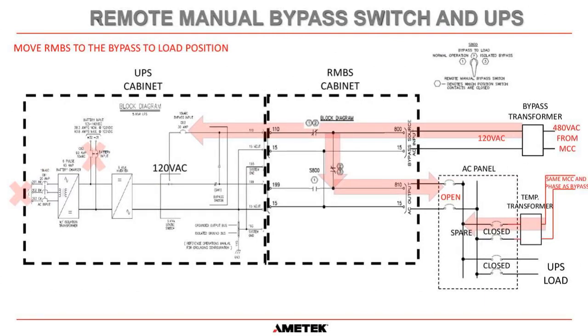Now we move the RMBS, the remote manual bypass switch handle, to position 2. And as you can see here, position 2 there and position 2 there. There is no position 2 here, so that remains open. So this one here closes, this one here closes. And that allows power back into our UPS cabinet up to the bypass input breaker. So that's preparing us to be able to turn the UPS on and do some testing. We've still got this AC breaker, the main AC panel breaker, open, okay? Then we remove the lockout/tagout from the AC input. Here we remove that lockout and we remove that lockout, and that means we have AC available at the charger and DC available at the battery.